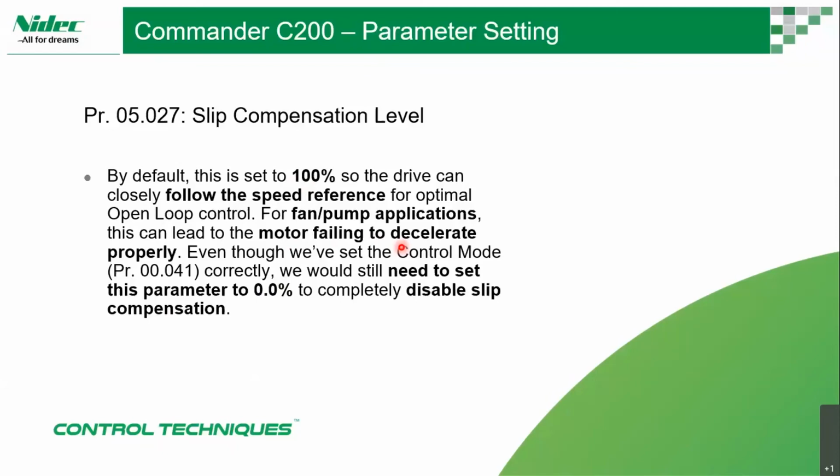The distortion is very bad for our inverter. Why do we have distortion? Because the inverter wants to make sure the slip compensation is 100% set to the same as the nominal. That's where the distortion comes from. We need to make sure this parameter becomes zero.